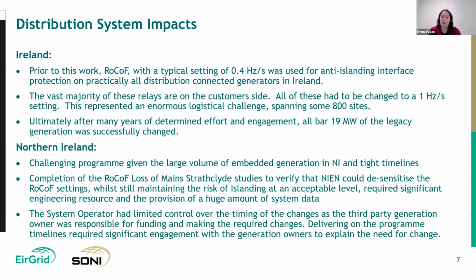In Northern Ireland, there were similar but slightly different challenges. Again, a lot of the renewables is embedded on the distribution network. The tight timelines were a challenge as well. The completion of the RoCoF loss of mains Strathclyde studies, to verify that the DSO could desensitize the RoCoF settings whilst maintaining the risk of islanding at an acceptable level, was required, and it required huge resources on their side and a lot of system data as well. And the limited control that the system operators had was a challenge too.